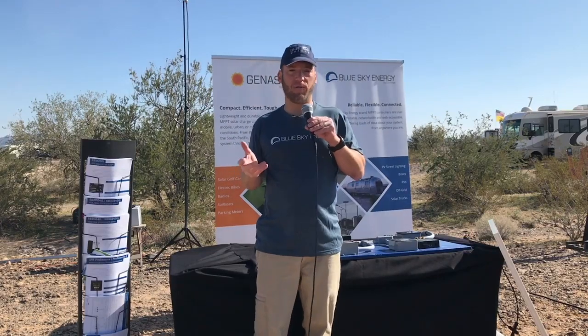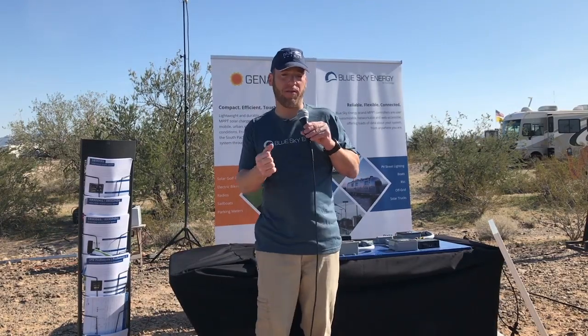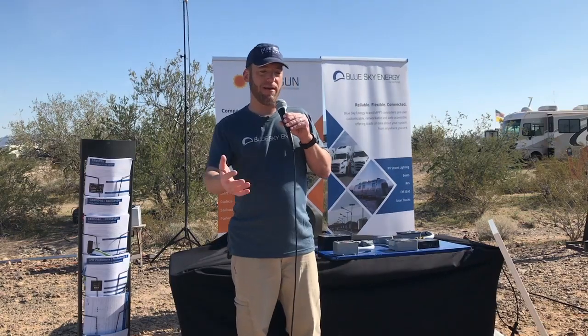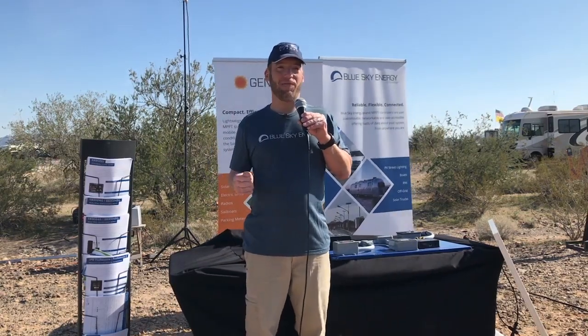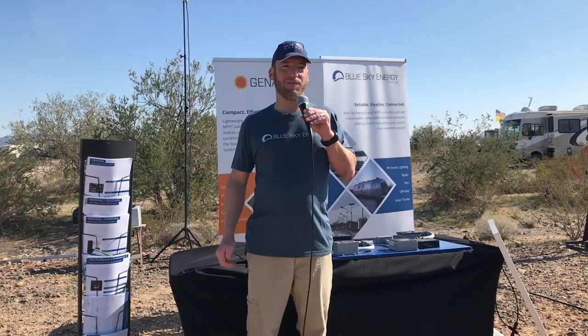Also, speaking a little about trying to get to the equalization voltage, I've had customers that did have enough power, punching out 30 amps, and they're like, Ryan, these 3 old Trojans, I finally went to equalize them because you told me it was a good idea, and they've been cooking for like 3 days, and I just can't get them above 15.7 or 15.8. I'm like, well, set your equalization to 15.7. Your batteries became sulfated, and they're just refusing to get to that higher voltage.